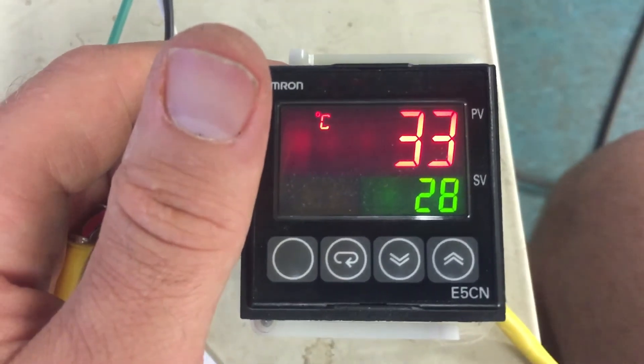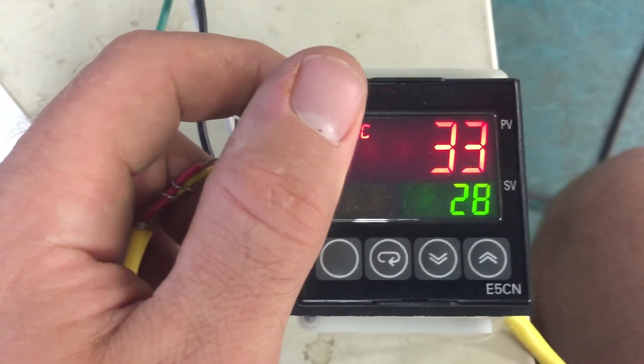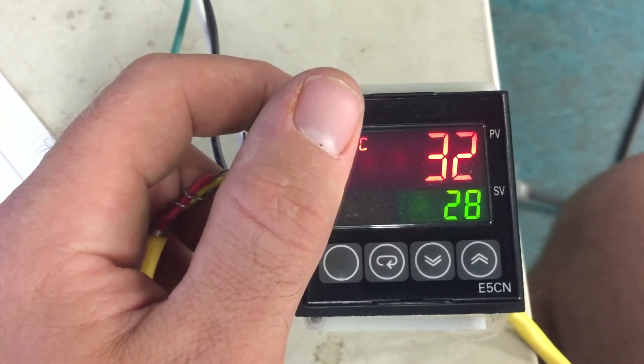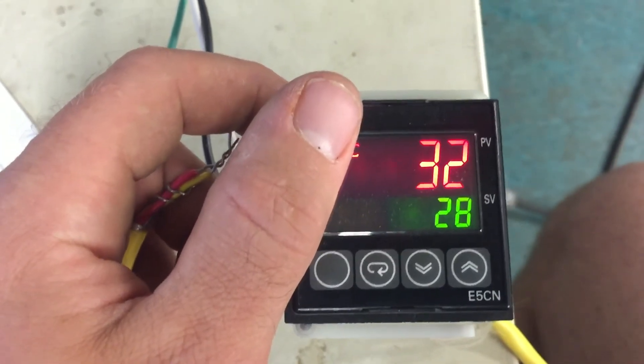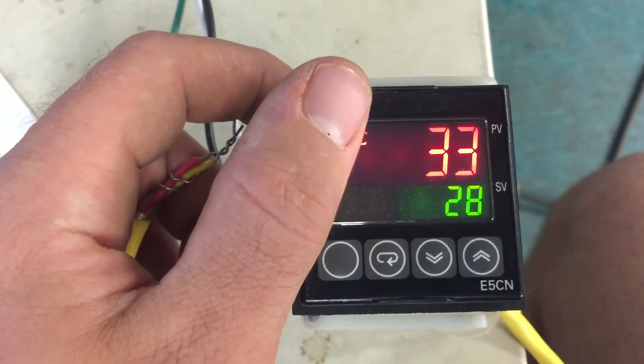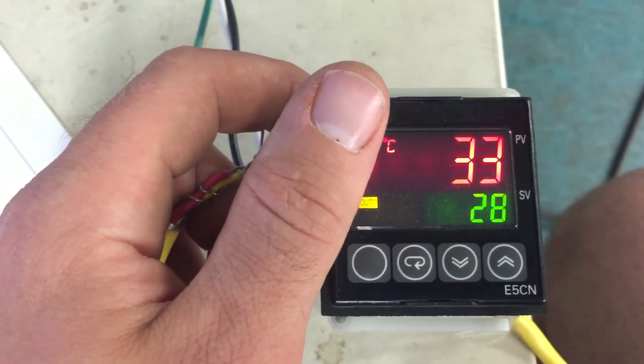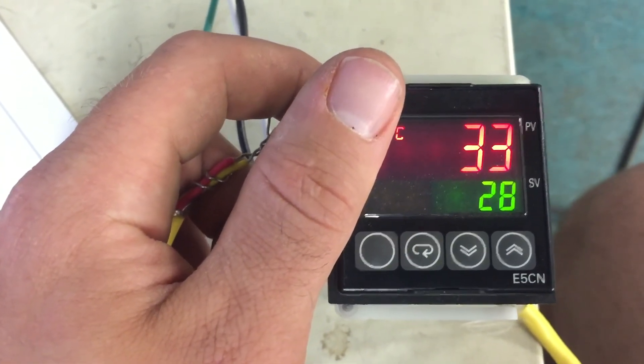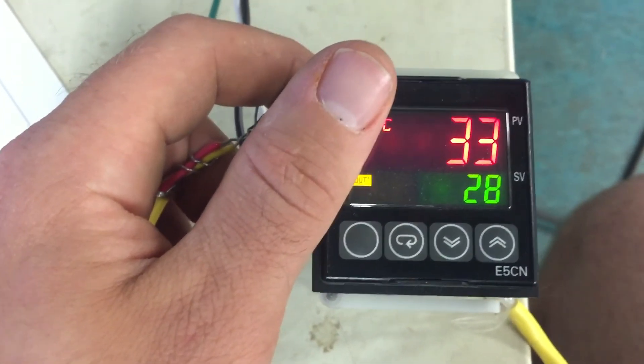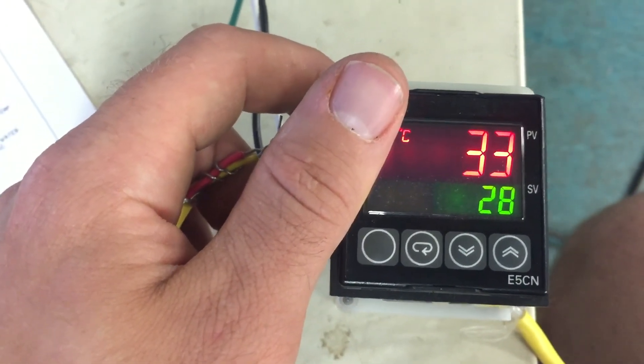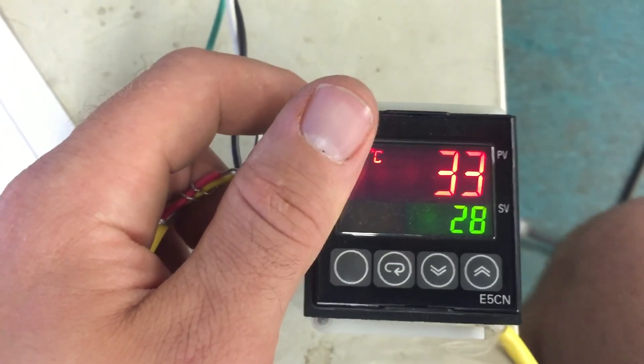Adjusting your needle valves on the water line will help with this. You should see a temperature increase of maybe one to two points maximum per second. Any more than that, you don't have enough water flow. If you're not able to reach your temperature set value there, that means you have too much water flow. It's quite simple as far as setting up the constant flows for low fire and high fire that you will essentially adjust the rate so that the temperature will allow to climb slowly up to your set point and go past slowly and then the pulse output will start activating to make sure that it's caught and brought back down to your set value. And that's pretty much it.